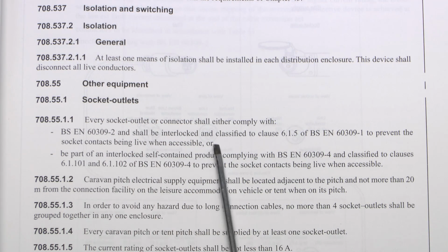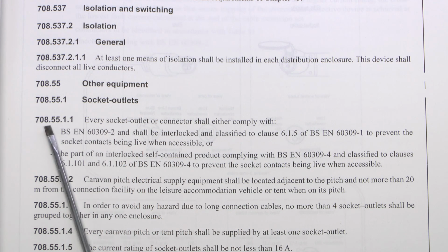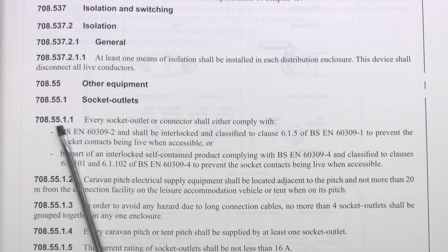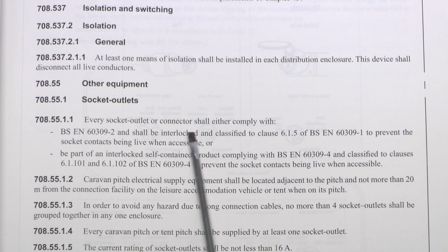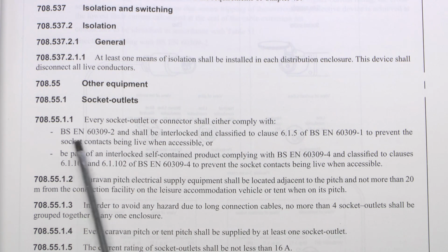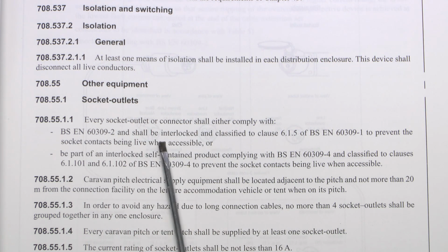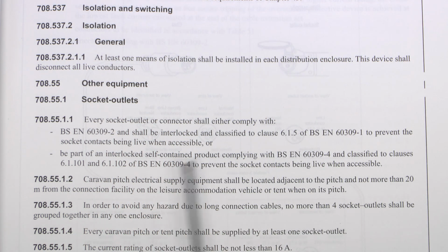One particular item here of note which is different to previously is 708.55.1.1, and we've now got that every socket outlet or connector shall either comply with the standard here and shall be interlocked and classified to this standard, or be part of an interlocked self-contained product, again complying with the standards here and there, to prevent the socket contacts being live when accessible.